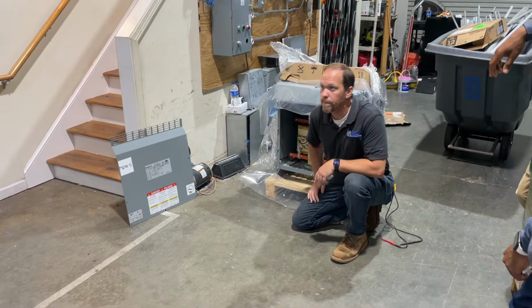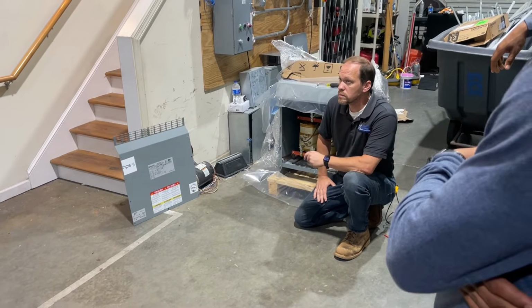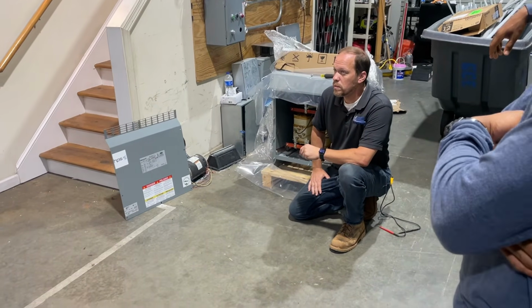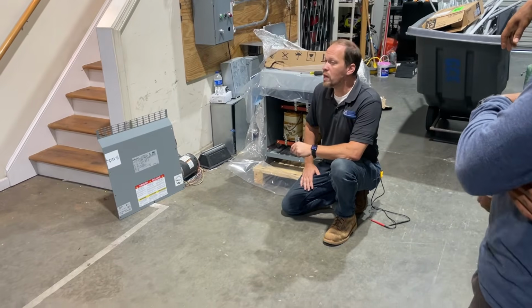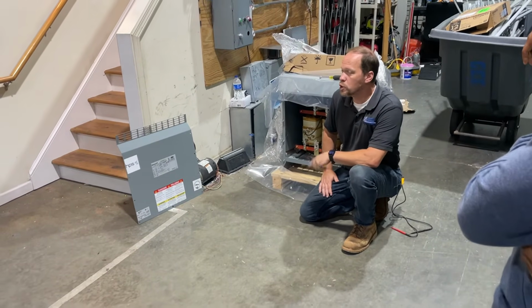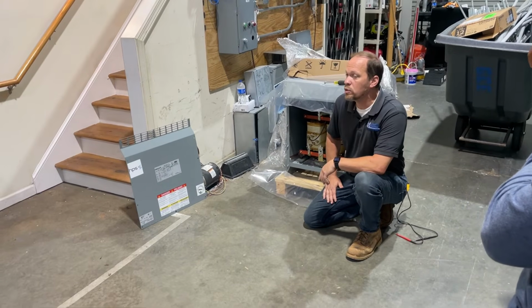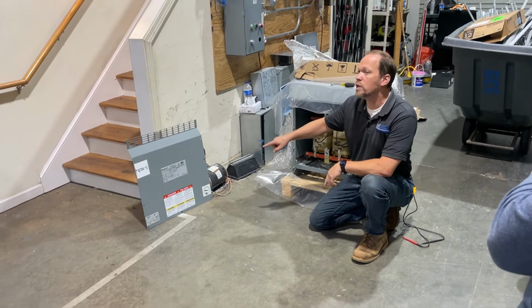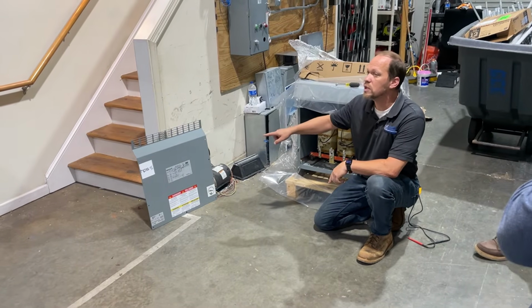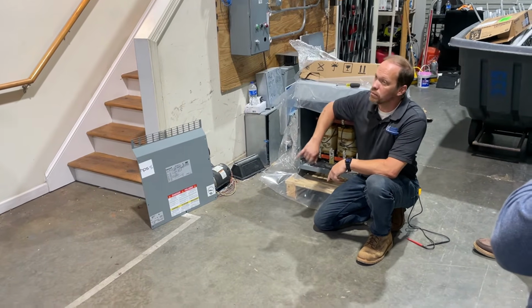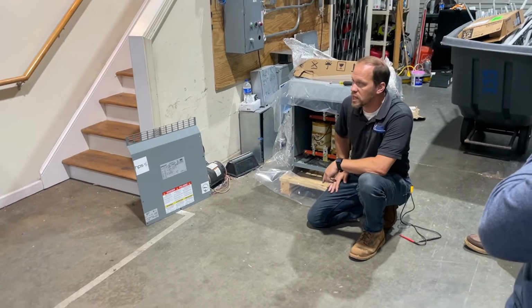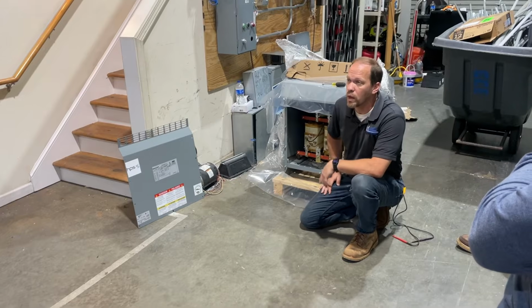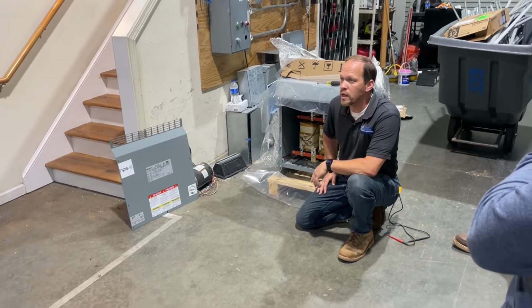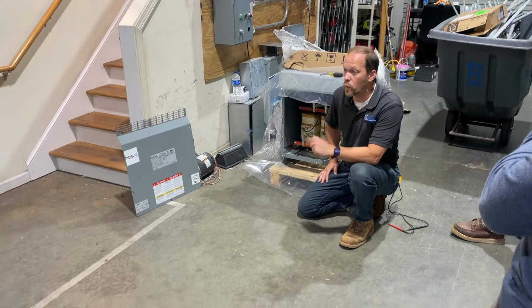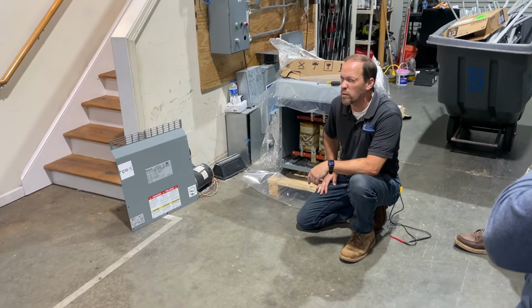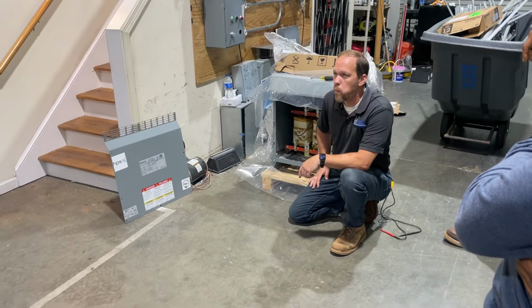So how do we come in with 480 but want to get 240 three-phase coming out, like what we did? All you have to do is reverse it—you use the ratio the exact same way. You won't know it based on these numbers, but you'll know what the ratio is, and that's why it's important to know the ratio so you can do the math backwards instead of forwards. You do it the exact same way, which is exactly what we did. They wanted 230 volts coming out, not 240, if I remember right.